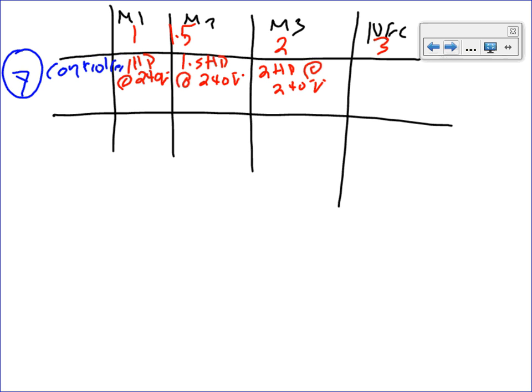What's the code reference? Thank you. The code reference for the motor controller is 430.83. Correct me if I'm wrong here. I've never been wrong. For motor controllers, it tells you to size it based on the voltage and the horsepower.